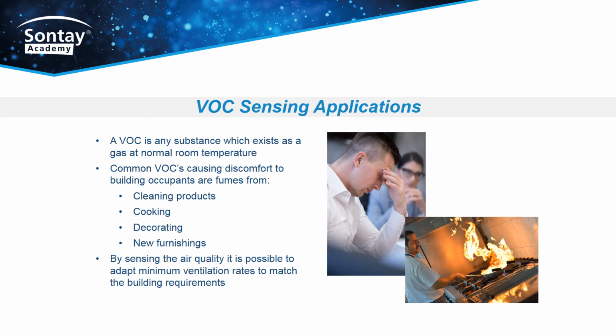Commercial kitchens are another space where VOC monitoring can be beneficial. Kitchen ventilation requirements tend to be high, but only when cooking is taking place. At other times, the ventilation rate can be slowed to match the activity in the space, thus reducing fan energy consumption, which can be achieved by sensing the concentration of VOCs within the space.